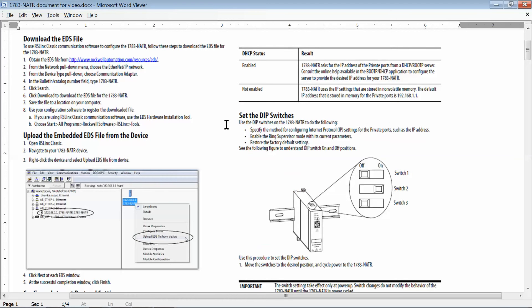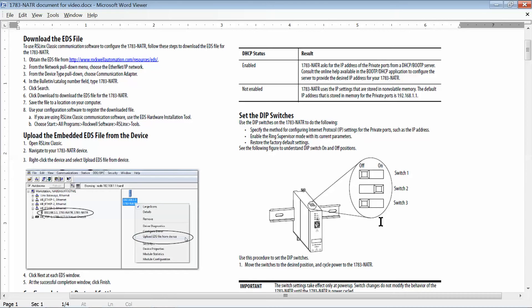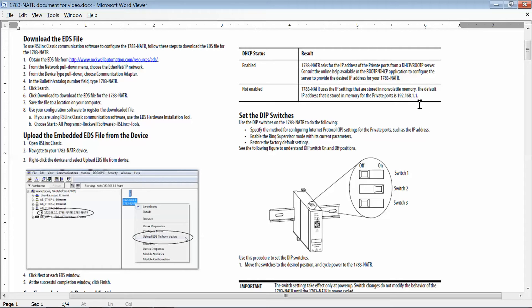Once you have your 1783 NATR powered on and plugged into the appropriate switches, what you're going to want to do is look at the switch settings on the top of the NATR. Set them as follows right here with switch two on, switch one off, and switch three off. That way it will give the 1783 NATR an IP address of 192.168.1.1.